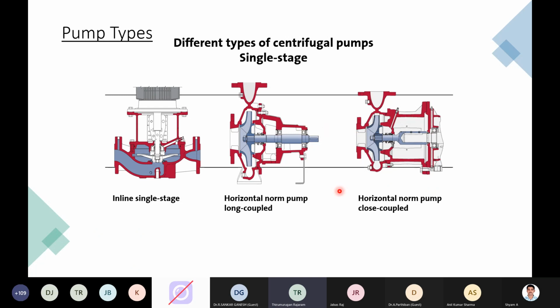Obviously, this coupling is also a sensitive part, where your coupling life is also affected based upon your situation. So that is also an important thing to notice. And here you can find there is no coupling, but still there is a stub shaft arrangement. It is close coupled. You are eliminating the coupling need, and you are eliminating a bearing need here also. So these designs have also been adopted in power plants.